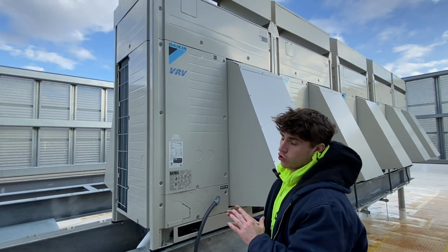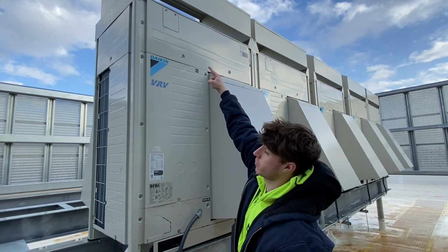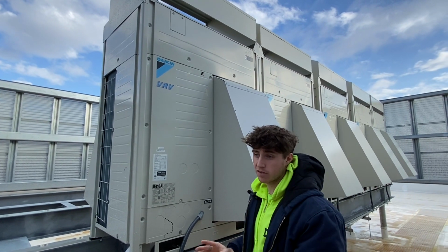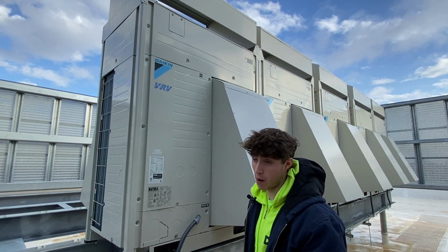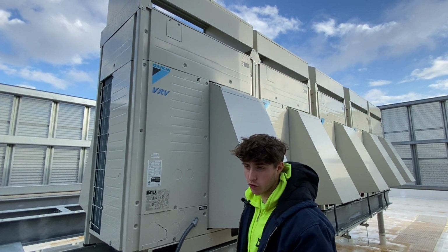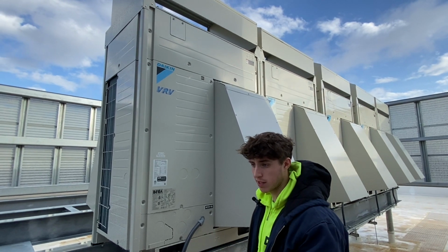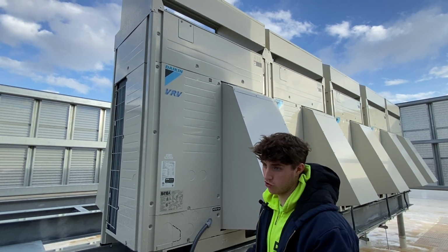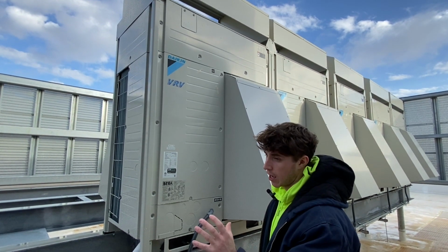If it shows blank screen, it's in normal operation on the screen up there. You shouldn't see any blinking lights or anything like that. It has to be normal operation, and it also has to be running too. So blank screen is normal operation. If it's solid zeros, it's trying to initialize or it's trying to pick up something. If it's blinking, it's still trying to pick up a lot of stuff, and it's not. It sounds like a communication issue could be going on too. So usually you want to have blank screen.